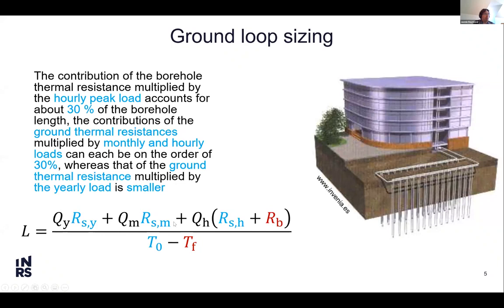So my blue parameter depends on the ground, the thermal state and property of the ground, while the red parameter are design parameter that I can improve to make my system more efficient. The fluid temperature, it's the temperature that I decide in terms of heating mode. The cooler is the temperature, the less efficient is the system, but those systems can have good efficiency working at 0 degrees Celsius, for example, for heating.